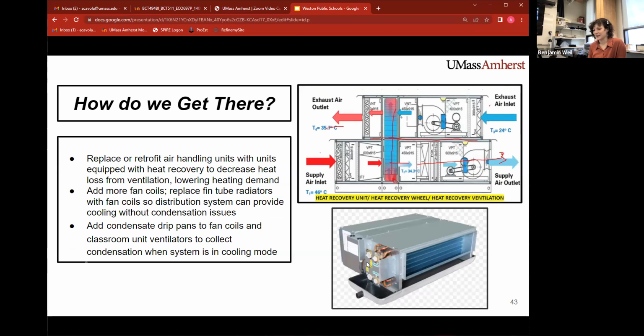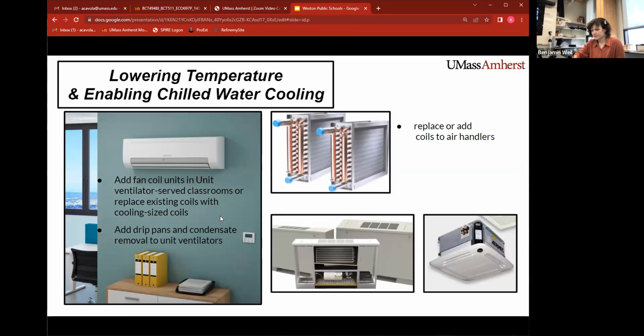So how does this work out in practice? Here are some changes we recommend to the existing building HVAC equipment to make ground source heat pump heating and cooling possible. Replace or retrofit air handling units with units equipped with heat recovery to decrease heat loss from ventilation, which will lower heating demand. Add more fan coils. Replace fin tube radiators with fan coils so a distribution system can provide cooling without condensation issues. And add condensate drip pans to fan coils and classroom unit ventilators to collect condensation when the system is in cooling mode. And here are some example fixtures.